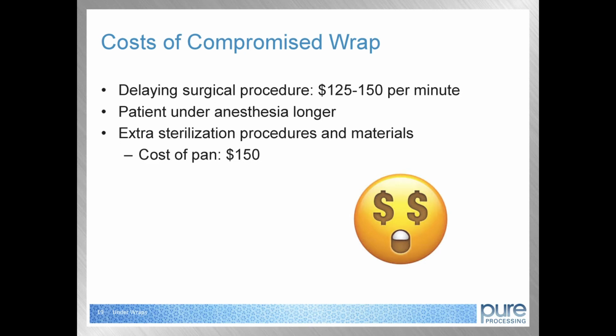That makes us have to do more work because we have to bring that pan down and re-sterilize it, which costs more money. An average pan to sterilize runs $150, from the time you wash it, inspect it, do the layers, put the indicators in, wrap it with CSR wrap, decide whether to use corner protectors or whatever else you need, then autoclave it and set it off for 45 minutes. You're looking at about $150 a pan.